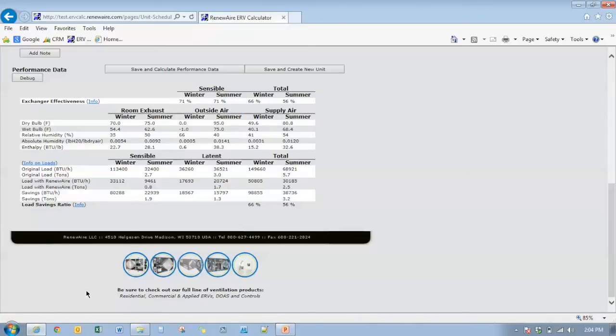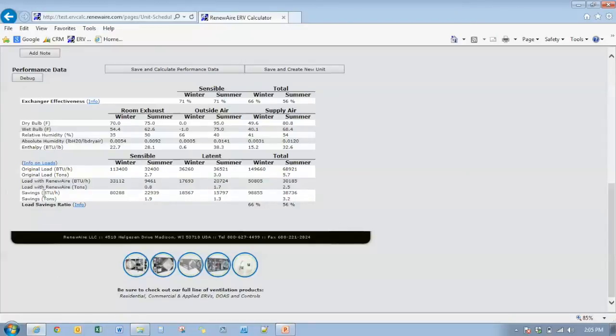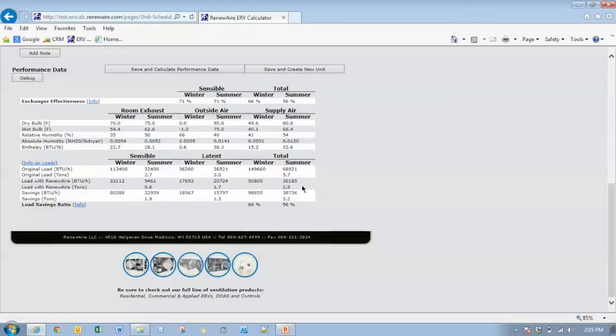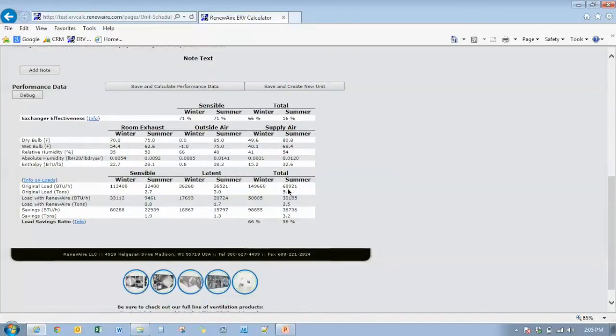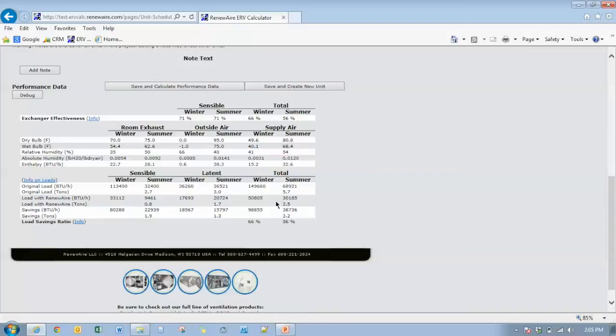We also, in addition to the airflow limits, as well as the exchanger effectiveness, we changed the method that we're calculating the loads of the building. In the past ERV calc, there was outside air loads for infiltration or exfiltration or additional outside air coming in through other sources of the building that were calculated into those loads. Now we're only looking at the fresh air stream. In this case, 1500 CFM of fresh air coming in and what is the load impact only associated with that 1500 CFM of fresh air that's being introduced to the building.